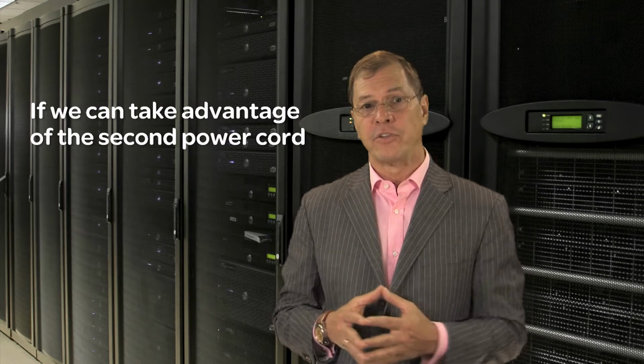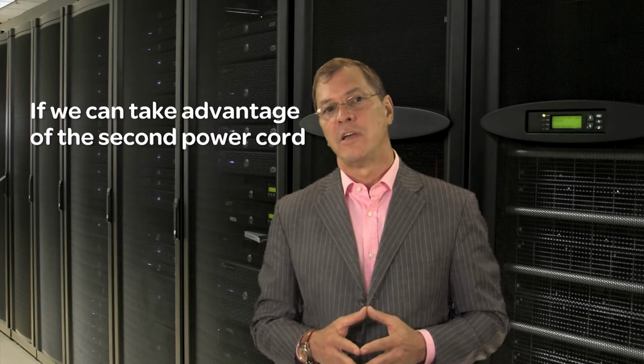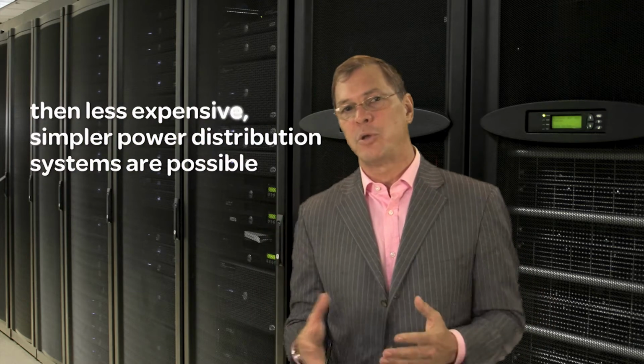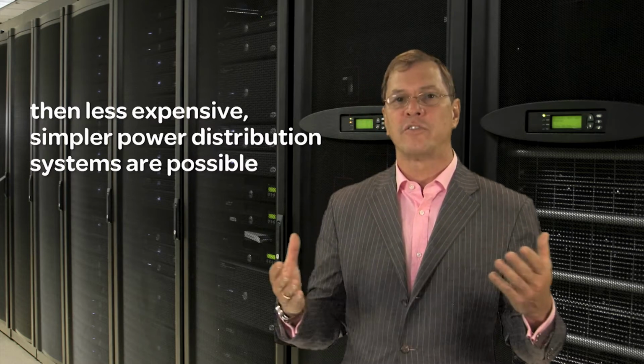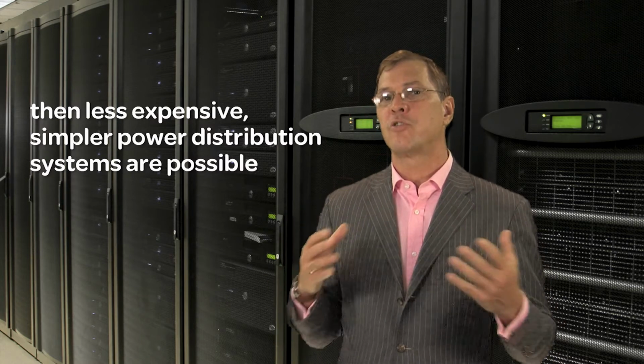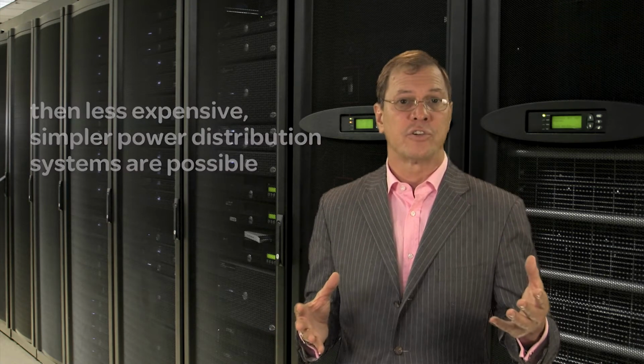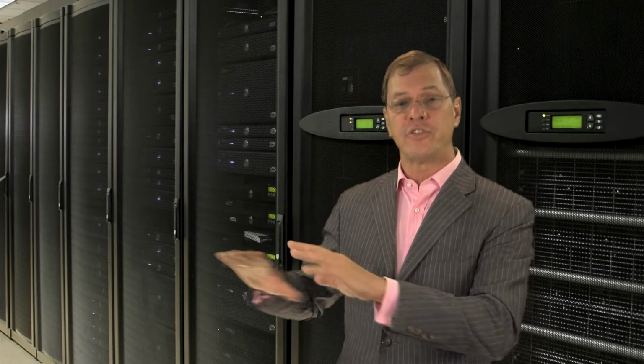Now, if we have a uniform IT infrastructure, and in that infrastructure we have improved knowledge of the status of the IT device power supplies, we can take advantage of the second power cord on the IT equipment as part of our redundancy design and use less expensive and simpler power distribution systems, such as, for example, what we have historically called Tier 3 type power architectures, which when combined correctly with a server where we understand its performance can give us Tier 4 performance with a Tier 3 physical infrastructure investment.